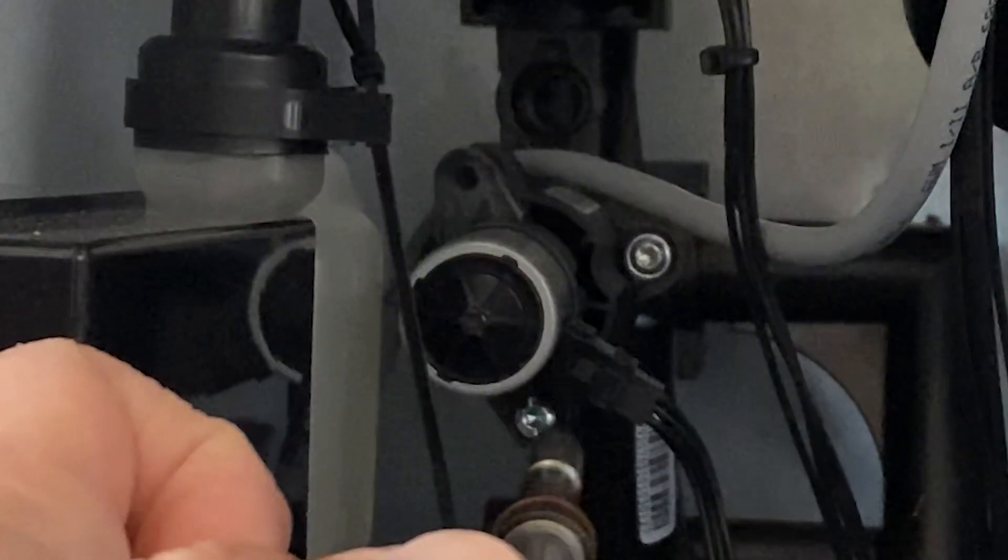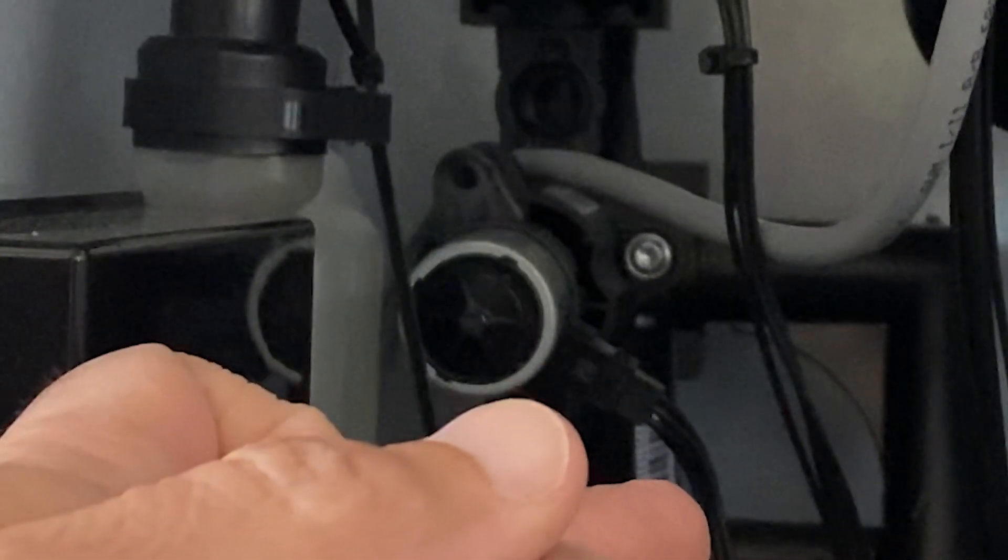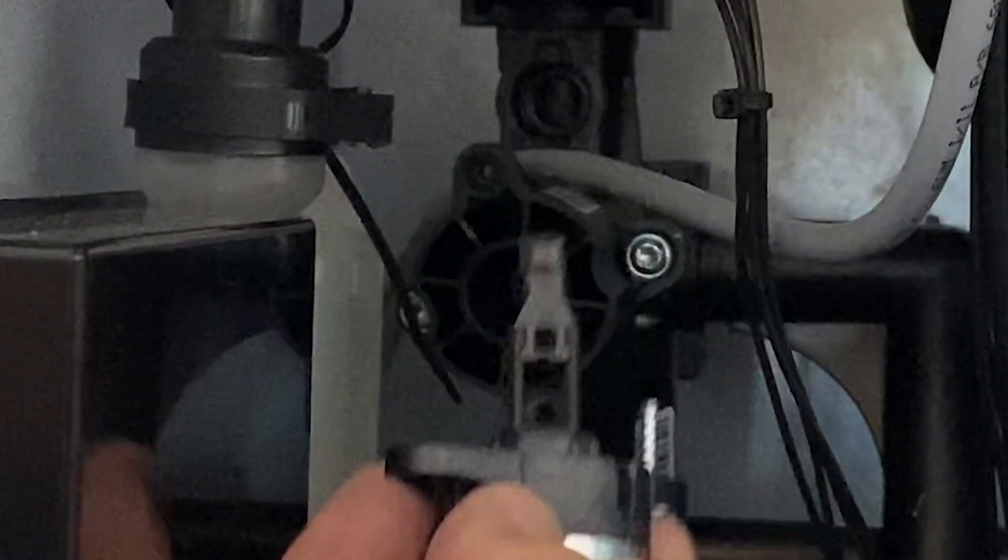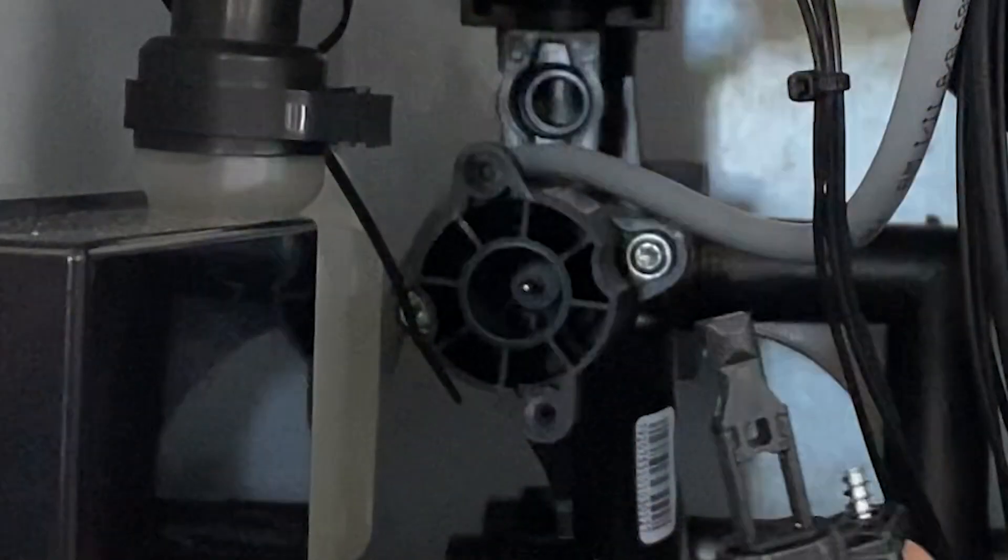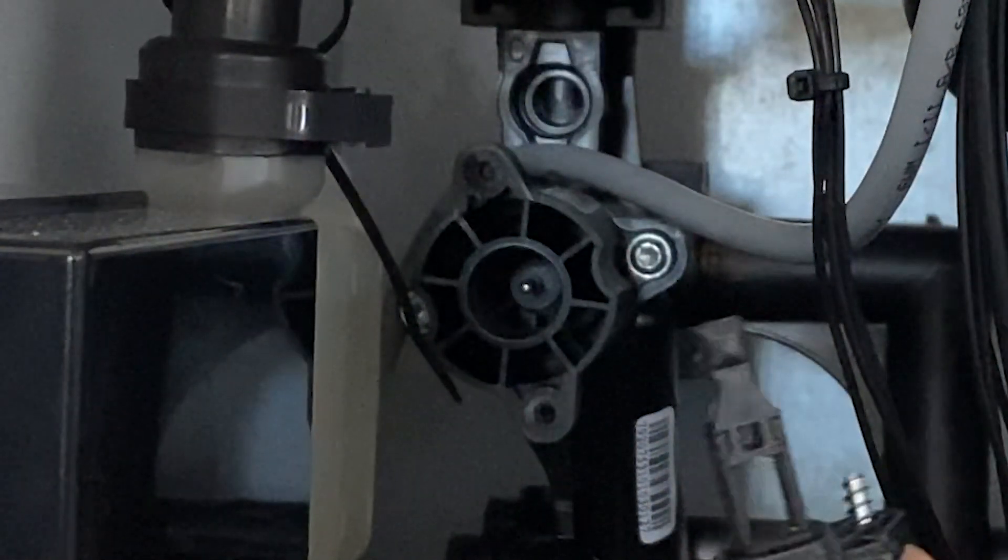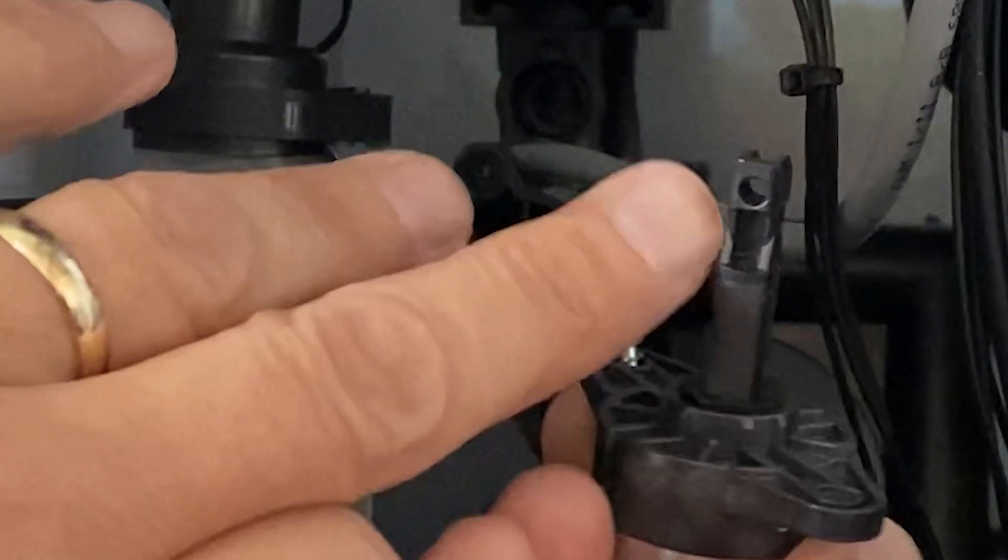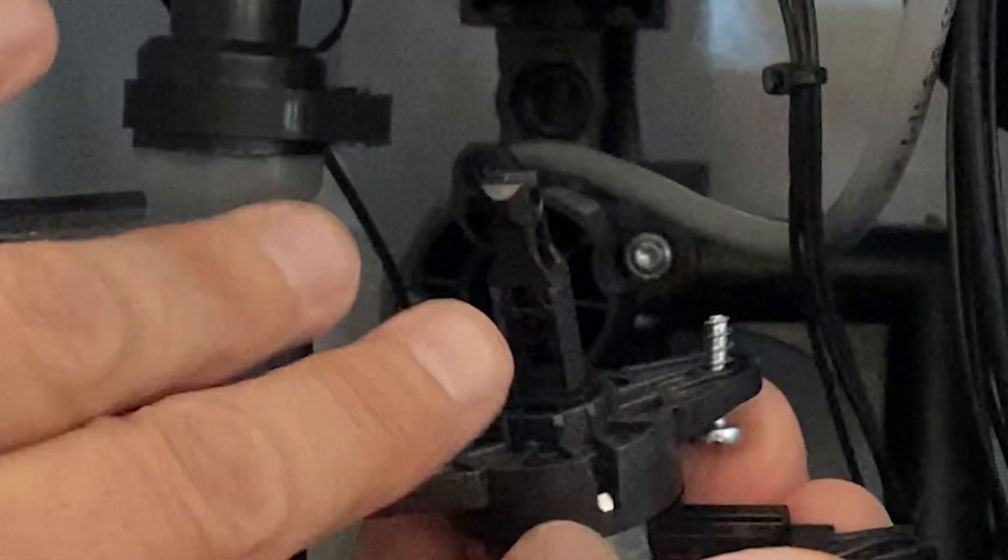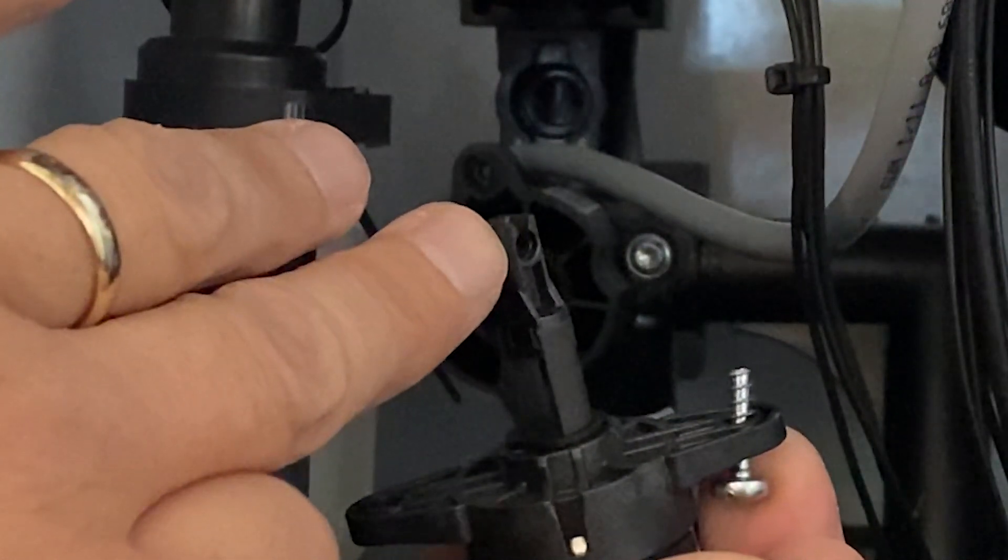At this point if I want to do a more aggressive exercise of the valve body, or the valve actuator, I can remove the motor from the stem. Now one thing to keep in mind here is the actual stem on the actuator has an opening. And you'll see one side is open to accept the actual shaft, one side is closed.